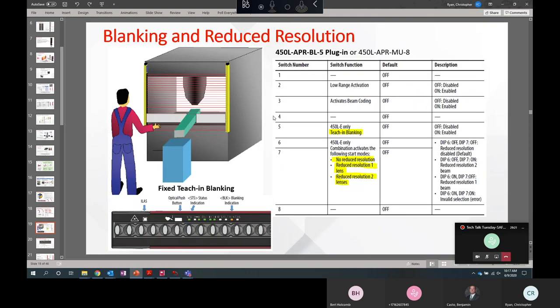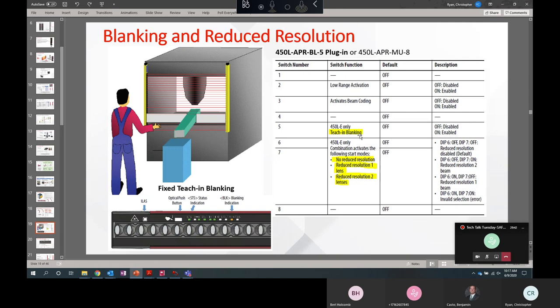So the next enhanced function we're going to talk about is blanking and reduced resolution, only configurable in parts of the 450L-E. Blanking allows objects that are wider than the optical resolution to pass through or stay in the protective field without causing a stop. These functions can be enabled with the blanking plugin or the muting plugin. So those are the part numbers for those. This is showing the DIP switch settings on the blanking plugin. The DIP switch numbers will be a little bit different on the muting plugin, but same idea here. So this is fixed blanking. This is the simplest form.